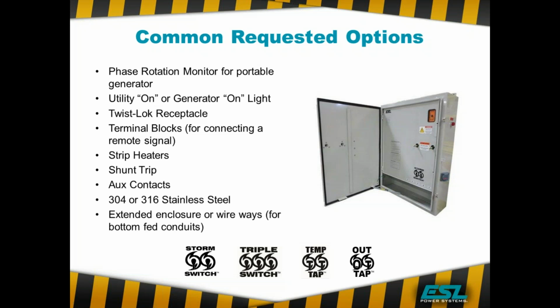304 and 316 stainless steel are available for the units. Keep in mind that when you have a riser drawing and you'd like to designate the enclosure to be stainless steel, the proper designation would now be NEMA 3RX. A lot of people in the past would call out for a NEMA 4X. And as we talked about previously, you really can't do that with most of the transfer switches and docking stations because you have holes in them in order to bring in the cables. So it was kind of confusing. So NEMA went back and provided the designation of NEMA 3RX for units that are going to be stainless steel.